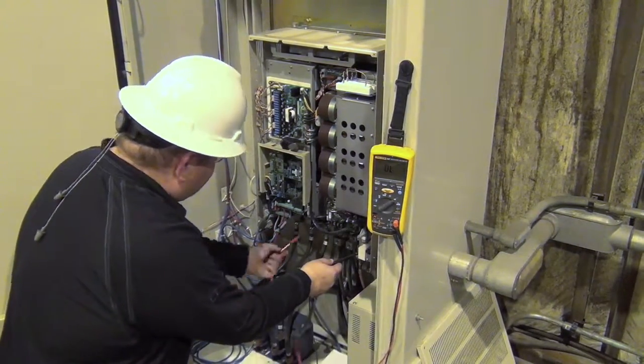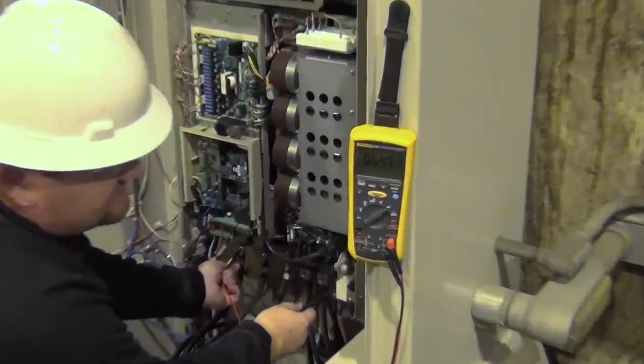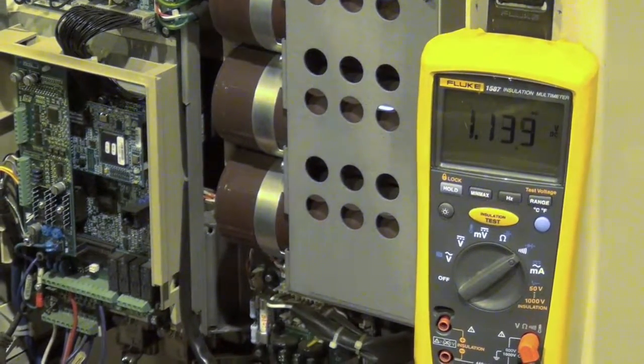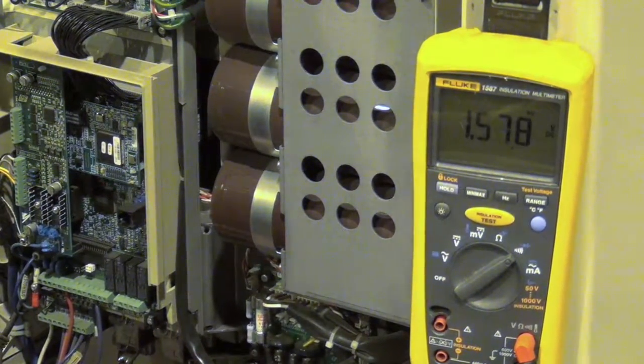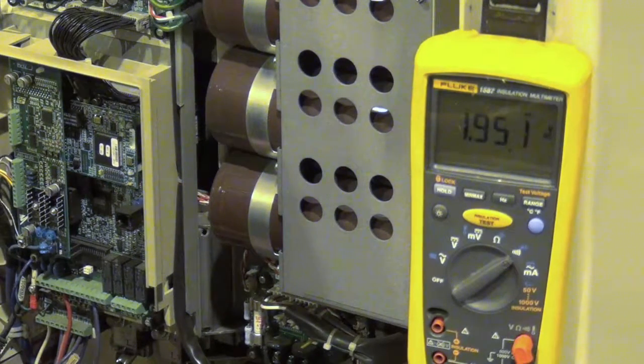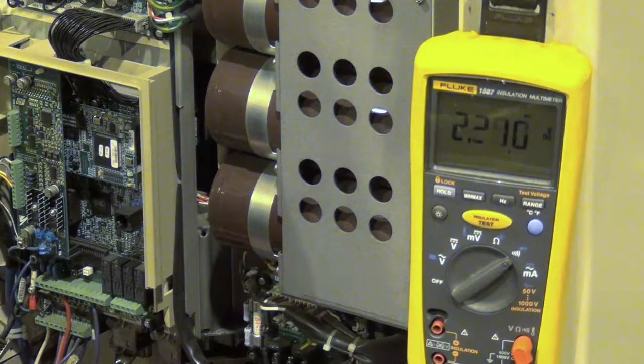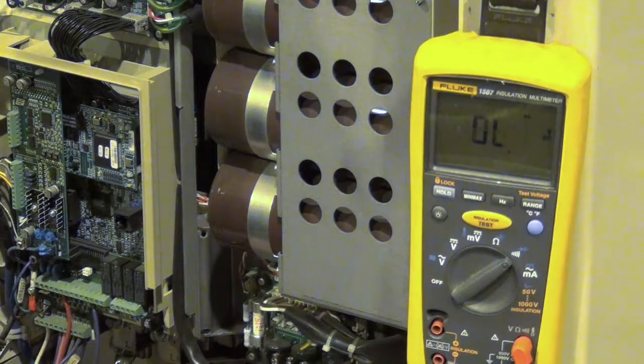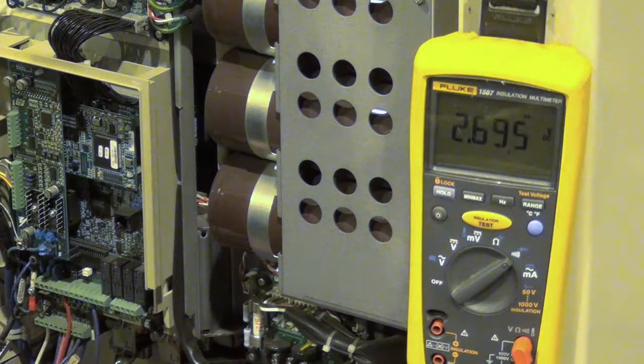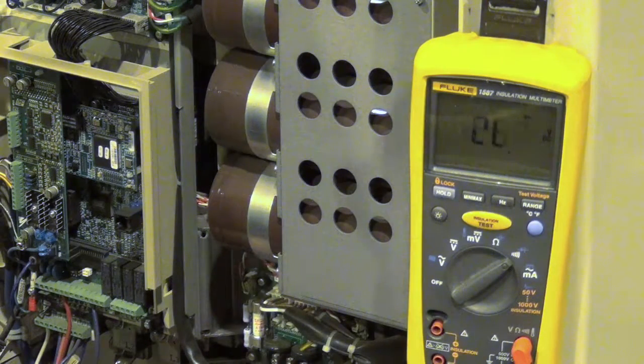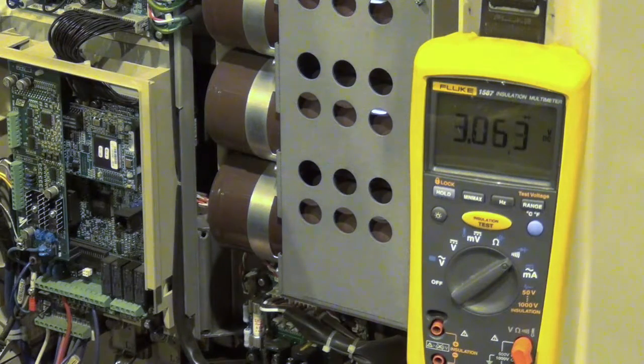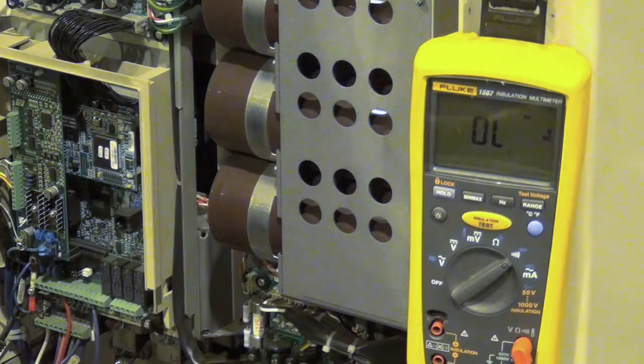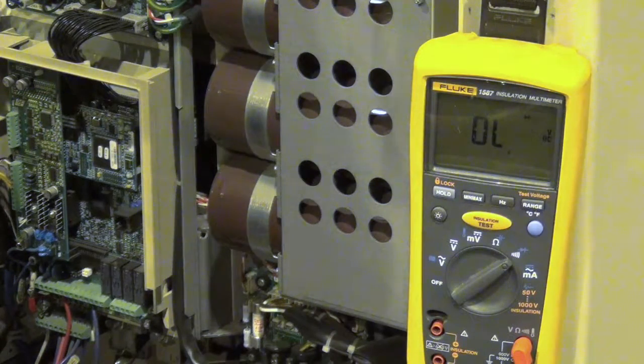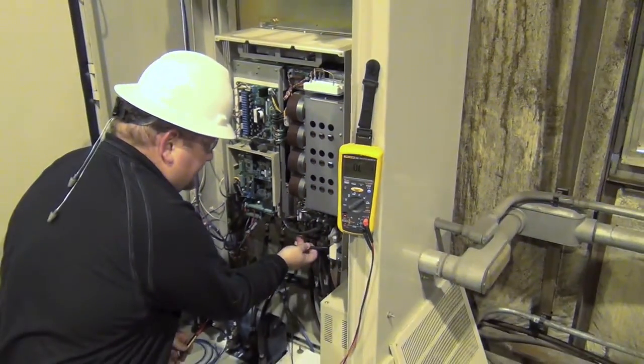I'm going to go with the black on the minus terminal, and I'm going to come across. So what you'll see is a value that slowly builds. So with this size of a drive, my meter is basically charging up the DC bus. So as long as we see it continue to rise, we can treat that as an OL reading. We can go to the next phase, and it should pick up pretty close to where it just was. So again, it's in the 2 point something, it's continuing to climb. So that one is still good. And we'll come across the other one, and again, same thing, it picked up roughly where it was and continued to rise.